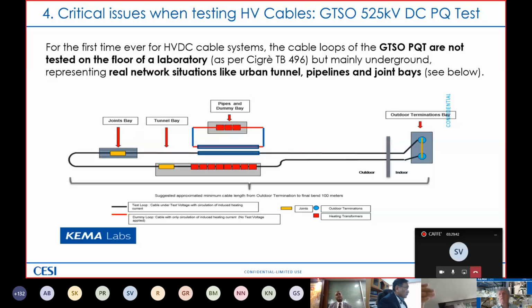I want to stress one very important peculiarity of this German TSO 525 kV cable system PQ test: for the first time ever, the long duration test, the pre-qualification test on HVDC cables, is not performed on the floor of a laboratory like in Technical Brochure 495 or the IEC 62895. Sorry, Technical Brochure 496 and the IEC 62895. But mainly underground, representing the real network situation like urban tunnel, pipelines, and joint bay.